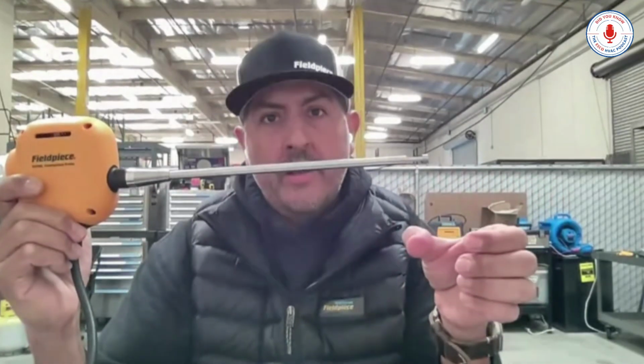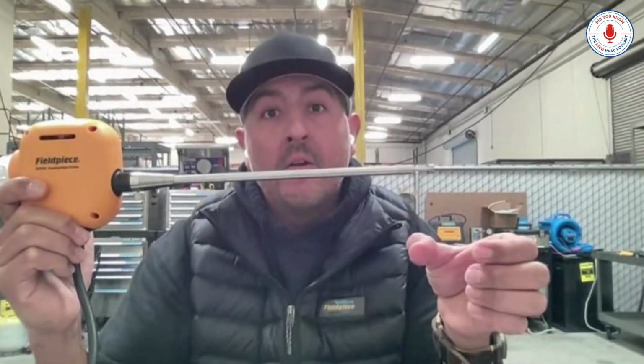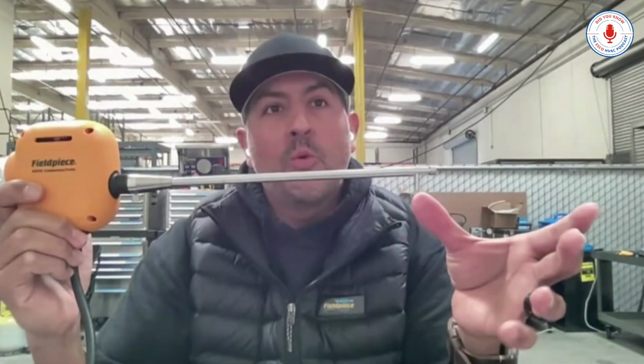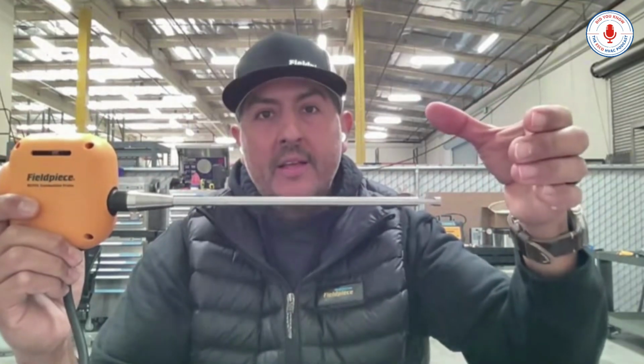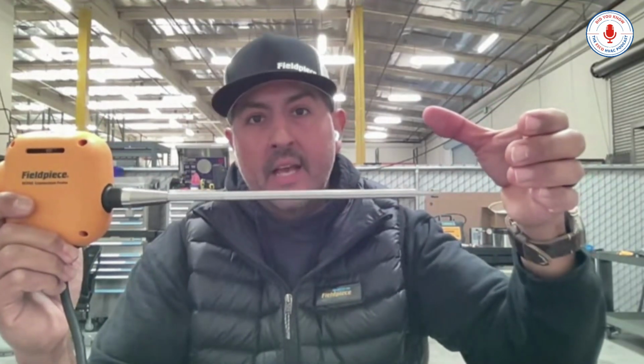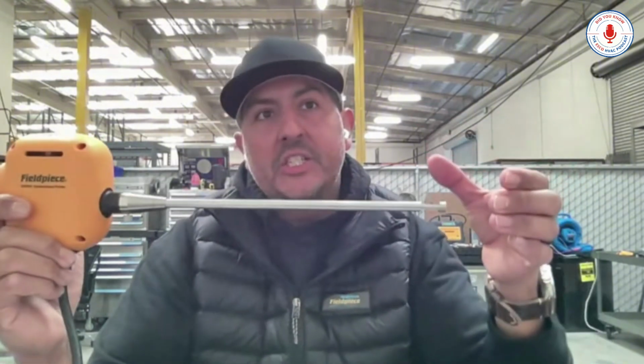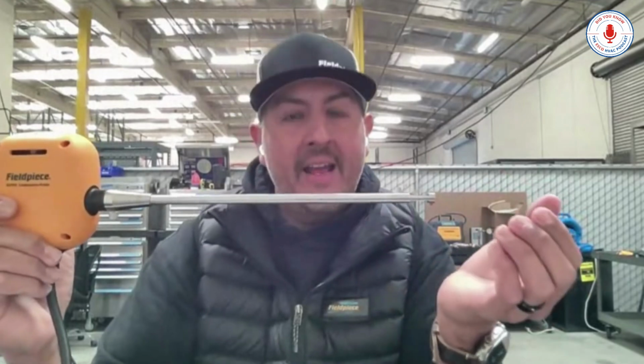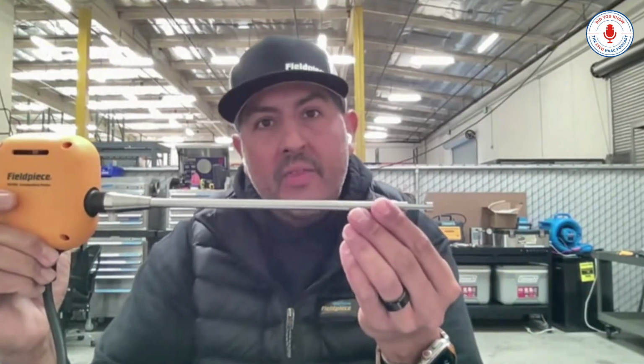So I would say it varies slightly on the size of the pipe, the flue. But for your typical high efficiency flue pipe, they're not very big. They're maybe a couple of inches. So generally, you should be fine just positioning the end of your probe in the middle of the flue pipe, right? If you're on another appliance where you have a much larger width stack or flue, maybe 4 to 6 inches, you would want to generally position it where you get the highest stack temp and the highest CO reading. But generally, if you're in the middle, you should probably be okay. Okay. It's good to know.